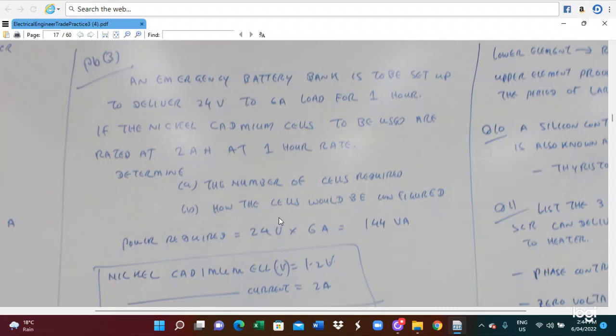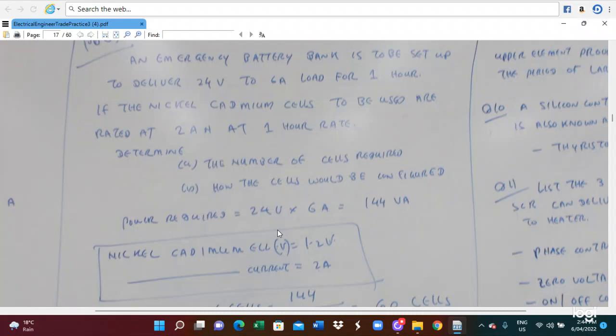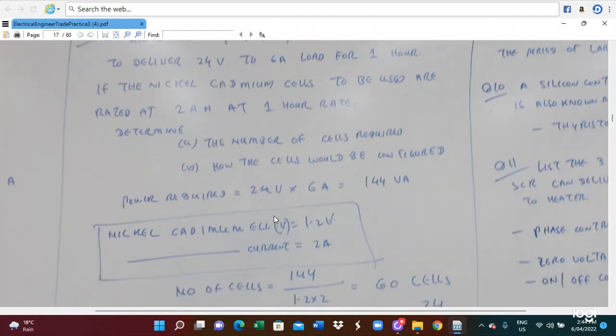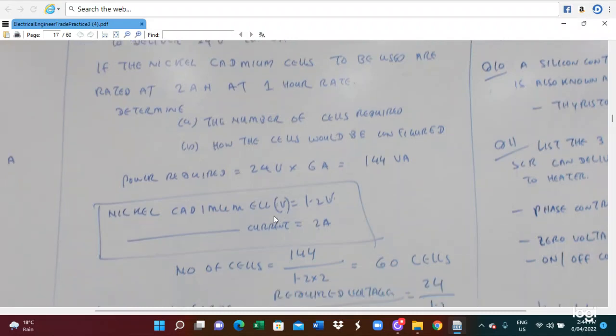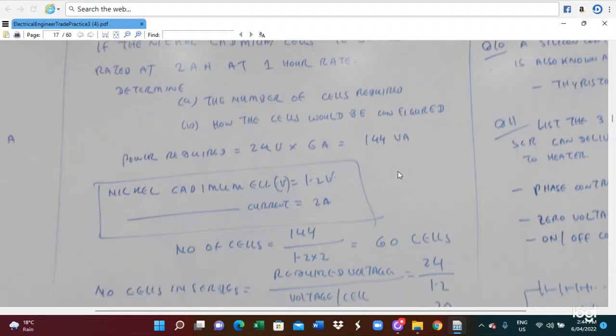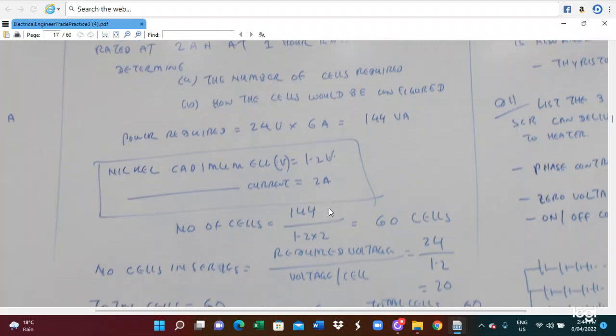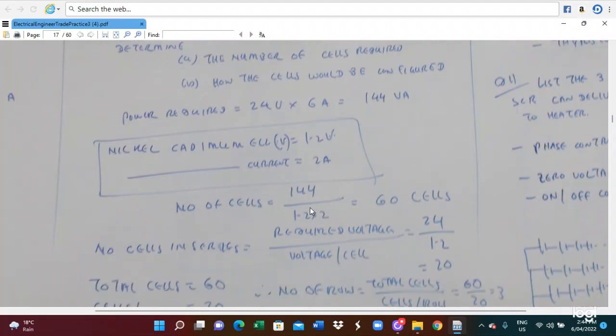The emergency battery bank is to be set up to deliver 24 volt, 6 ampere for 1 hour. The nickel cadmium cells are rated at 2 ampere hour at the 1 hour rate. We have to determine the cells required and how the cells would be configured. In this case, power required is 24 multiplied by 6, which gives 144. Each cell is 1.2 volt and the current 2 ampere, so the power is 1.2 multiplied by 2. So 144 divided by 1.2 multiplied by 2, you get 60 cells.